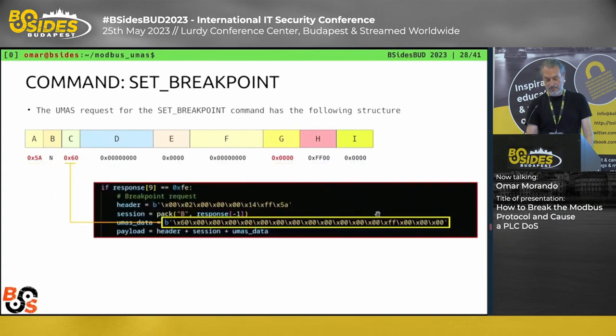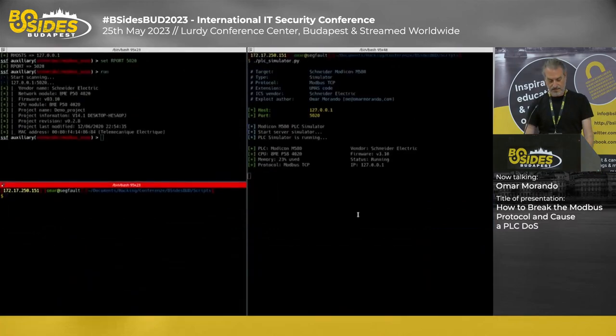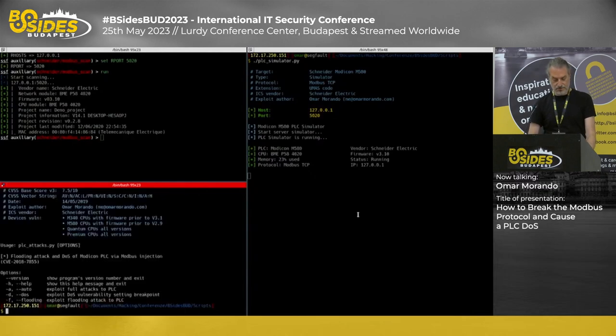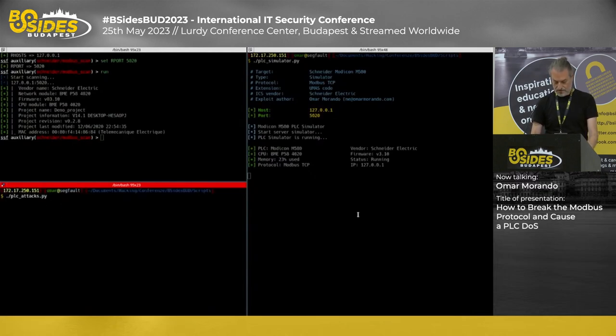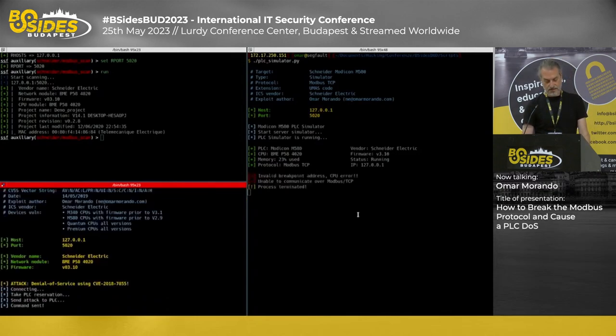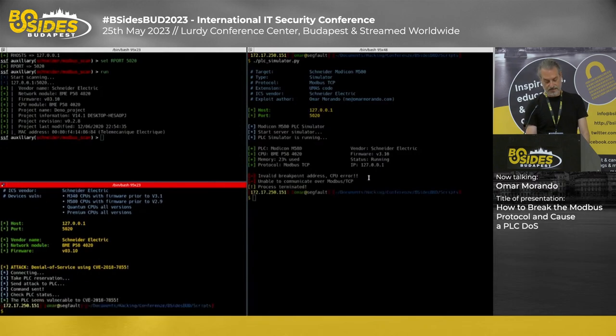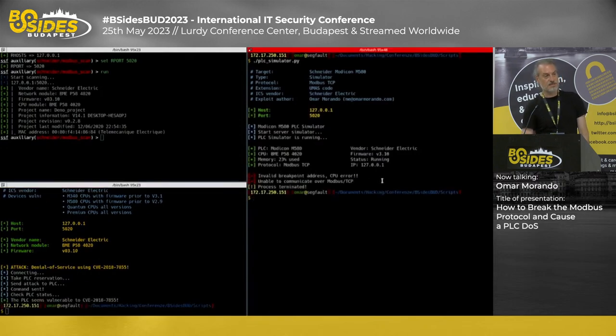So I can craft my packet, specify the 00 address, and using a very simple script, I have a simple tool, -D for denial of service. I can send this request, and the PLC is absolutely stopped because I reached an invalid breakpoint address, the CPU goes into error, and communication is completely stopped.